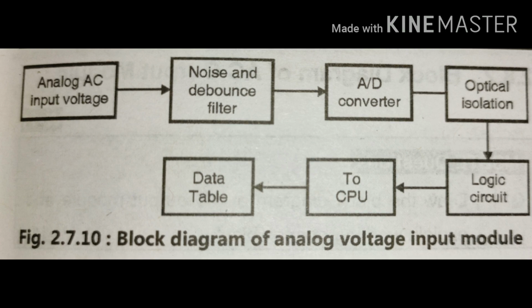An analog input module interfaces a PLC to analog input signals. It gives the PLC the ability to monitor continuously changing input signals representing pressure, temperature, flow, etc. The module converts the analog input signal to 16-bit binary values stored in the processor input status table.